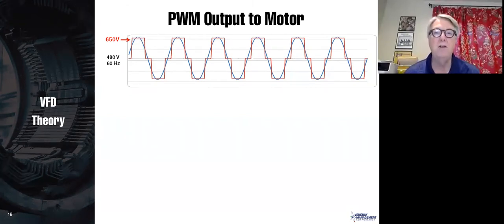So let's change the frequency to 30 hertz. If you remember from our last seminar, when you change the frequency to half, you must change the voltage to half. That's because the volts per hertz must remain constant. The drive does this automatically for you, so you don't really need to know that much about it, but it's good to understand why that is. So we can simply turn these things on and off slower, and we will reduce the frequency. But how are we going to control the voltage?